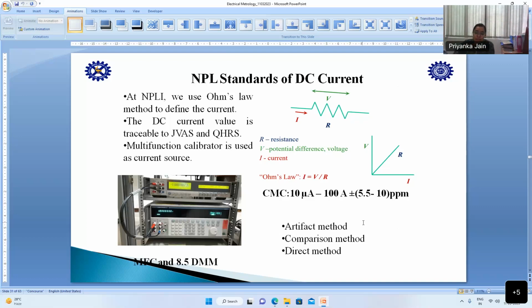So we have used many methods. That means we have the artifact method. Artifact method means we have Zeners and DC voltage dividers. Based on that, we generate current or voltage and we measure the values. Next one is the comparison method. That is, if we get a Zener for calibration, we have our reference Zener and we compare our Zener value with the customer Zener. Based on that, Zeners are calibrated. That is the comparison method. The last one is the direct method. Most of the DMMs which come here for calibration will be calibrated using the direct method. So we have a calibrated source, that is our MFC is calibrated. Using this, we can calibrate the DMM.